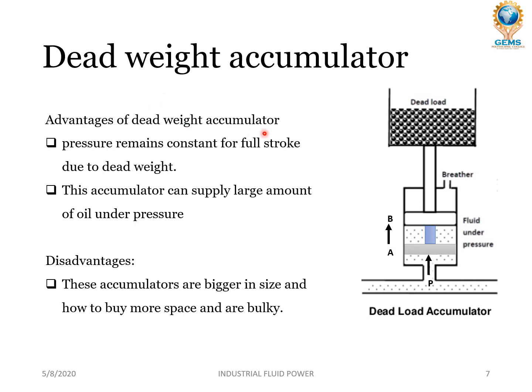The advantages of the dead weight accumulator are that the pressure remains constant for the full stroke due to the dead weight, and this accumulator can supply a large amount of oil under pressure. The disadvantages are that these accumulators are bigger in size and bulky.